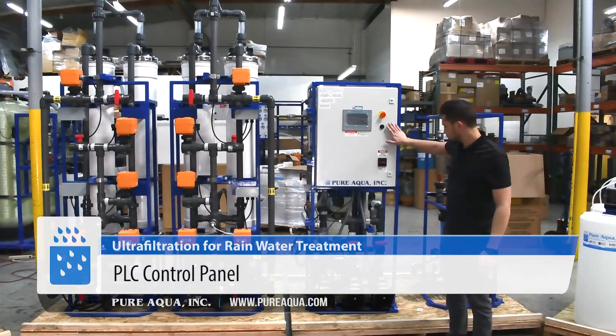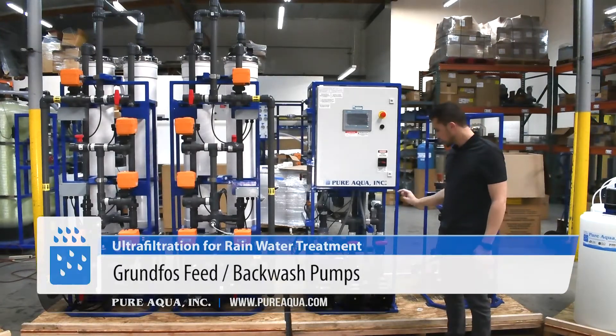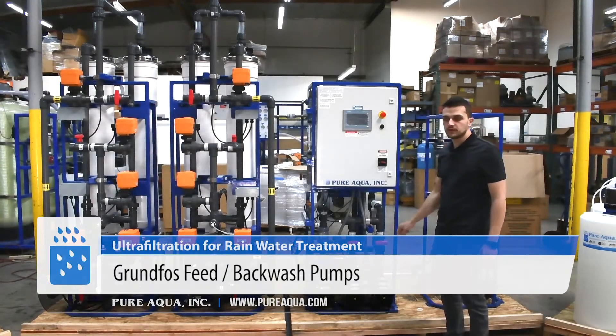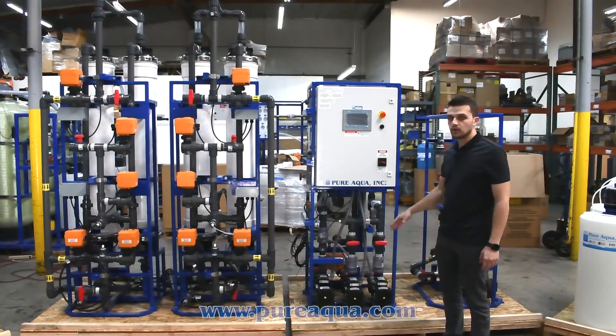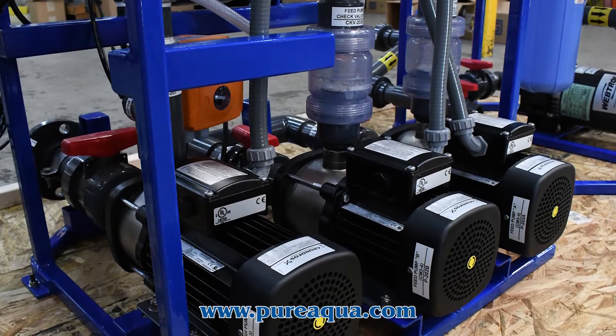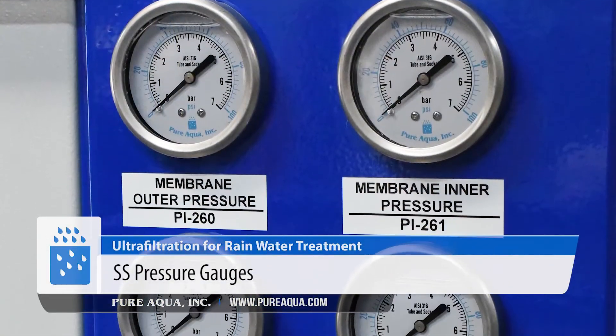The first unit here is our control panel and pumping system, where we have feed and backwash pumps. We have two feed pumps and one backwash pump. The feed pumps will alternate, and these are manufactured by Grundfos — they are stainless steel 316. After the feed pumps we have pressure gauge taps to monitor the pressure of the pumps.